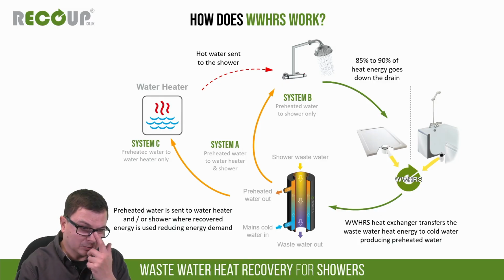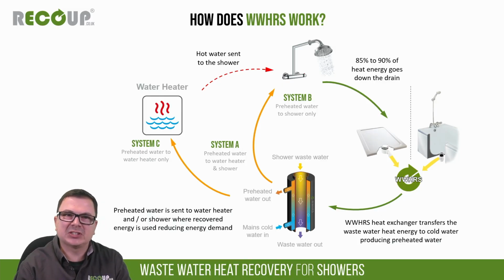Starting in reverse order with System C, a seldom seen system, this is where we simply send that preheated feed to the cold inlet on your water heater. For instance, with a combi boiler, we'd be sending a feed at around 25 degrees instead of a standard cold main at 10, so domestic hot water is produced more efficiently by that water heater.